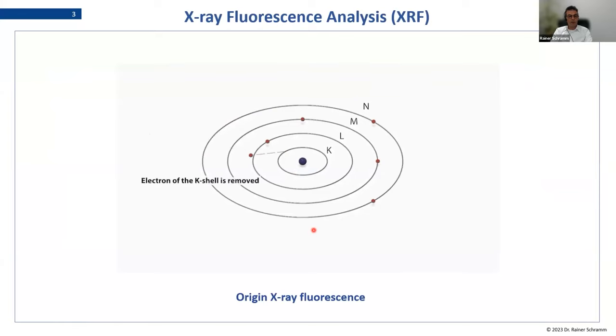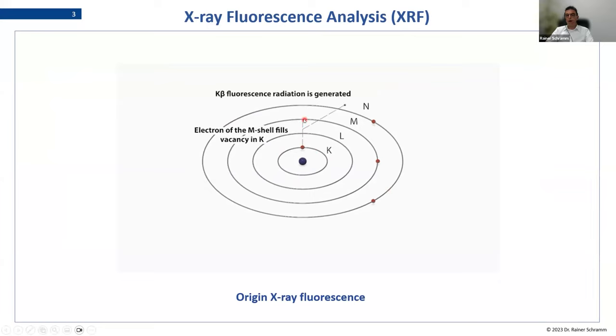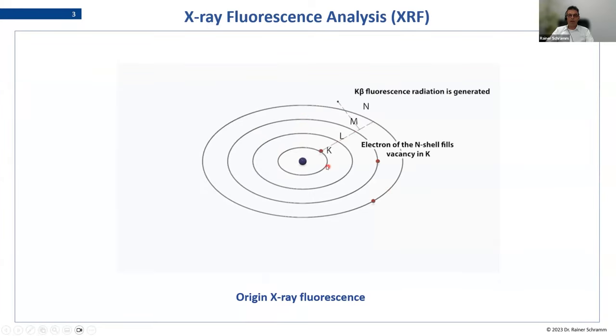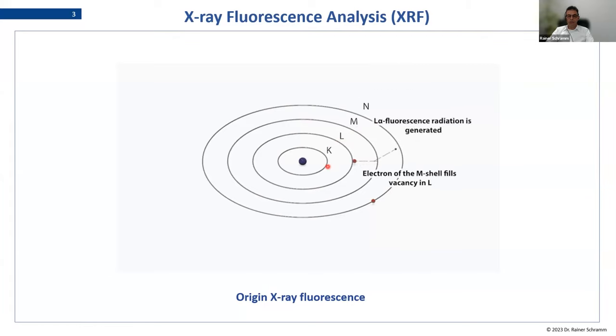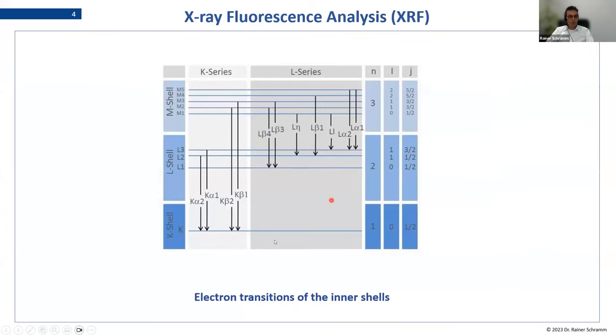To create X-ray fluorescence, you always have an excitation of your elements by an X-ray tube. This creates gaps on the inner shells, and electrons from higher shells fill that gap. While filling it, the energy difference is sent out as fluorescence radiation. We distinguish between different kinds of fluorescence radiation depending on which shell the gap has occurred in. We have the inner K shell, then the L shells and the M shells. If a gap is produced in the K shell and an electron from the L shell fills it, we call the line K alpha; if it comes from the M shell it would be K beta. Gaps in the L shell filled from the M shell produce an L line pattern.